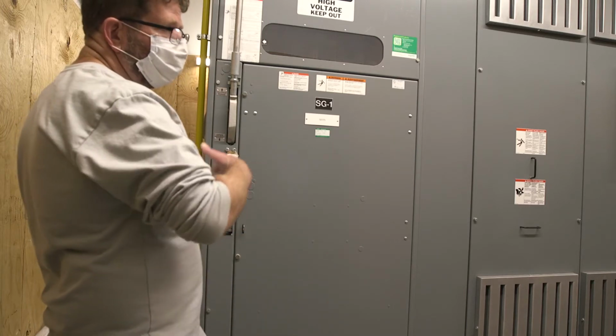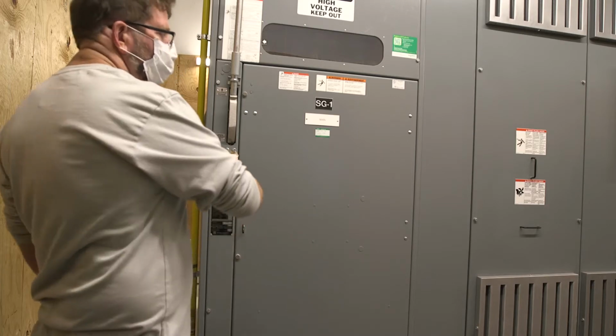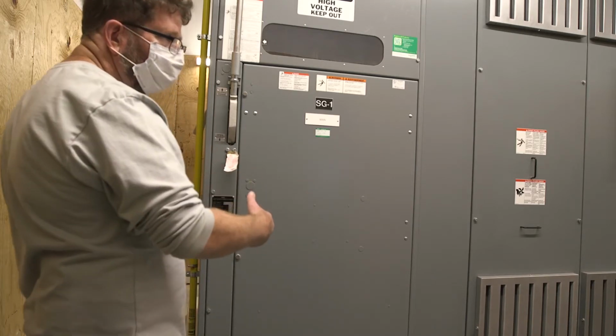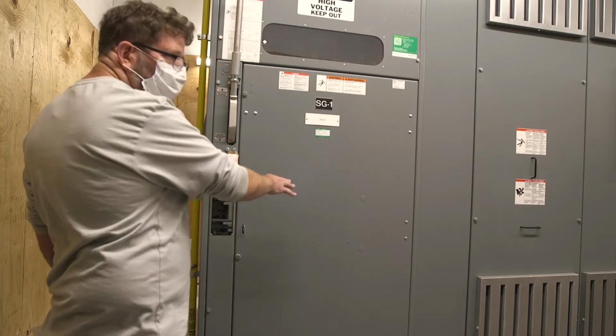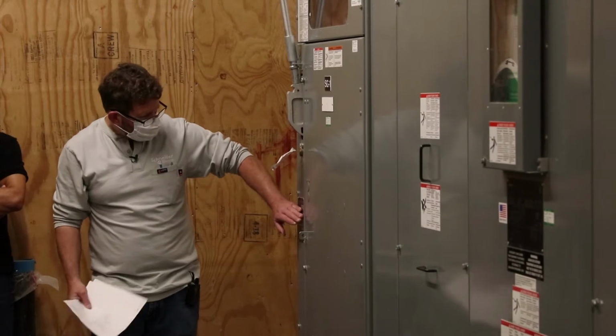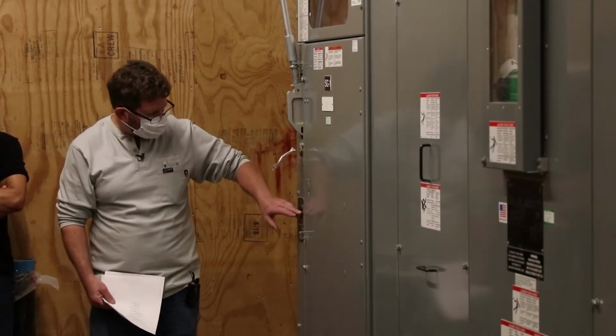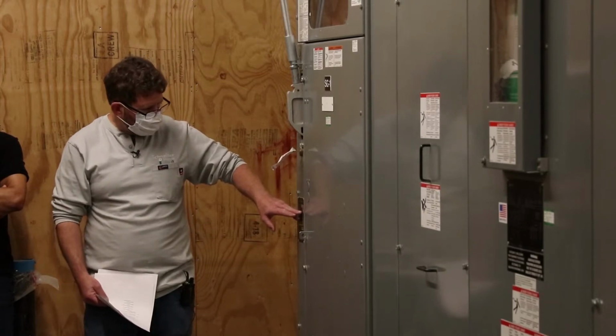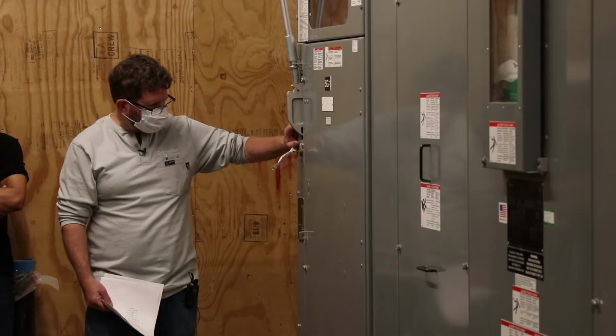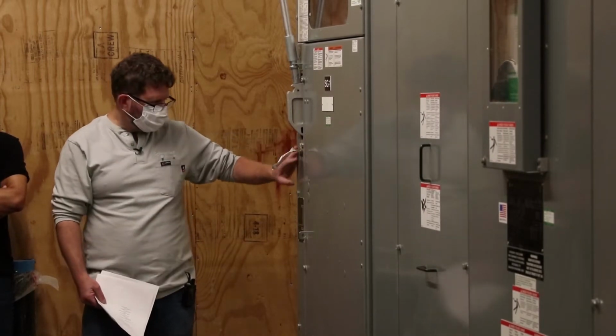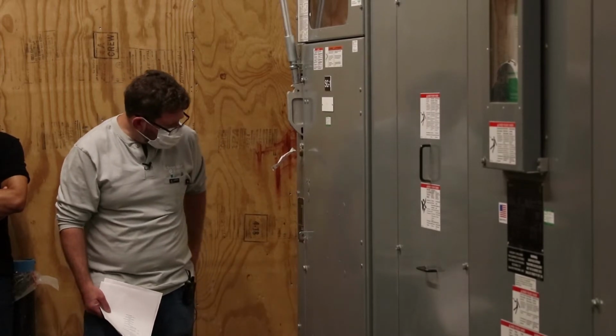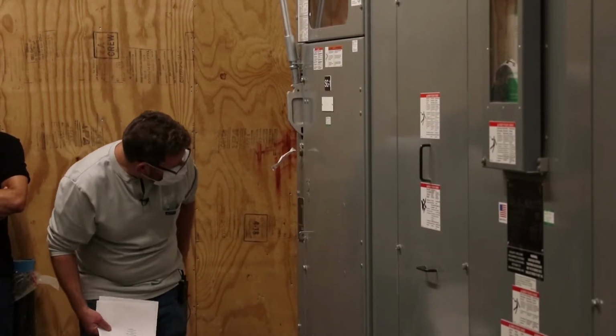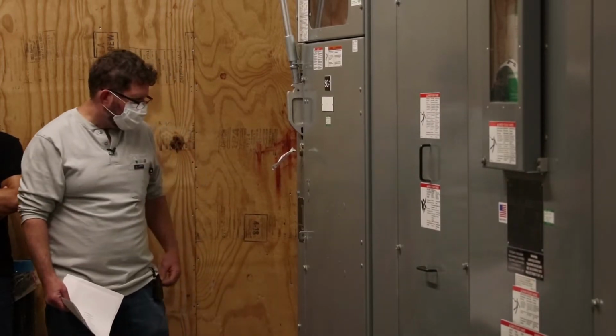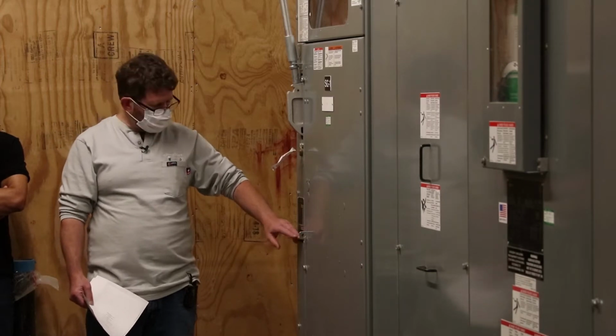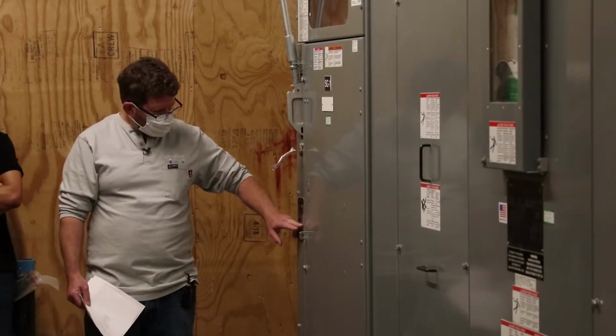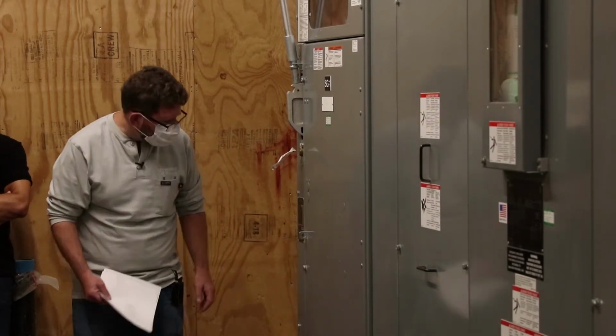So if you're calling Schneider for technical support, or parts support, anything along those lines, you'll need to have this number to reference what you're talking about. Below that is the part number for this switch specifically, the manufacturing date, and then it goes on to the different ratings. This is 5,000 volt rated. Impulse voltage rated is 60 kV. Interrupting rating is 18 kA, 60 hertz. Also on this is going to be your fuse sizes. You have the fuse part number for the fuses in here and the fuse size. It's a 450 amp fuse.